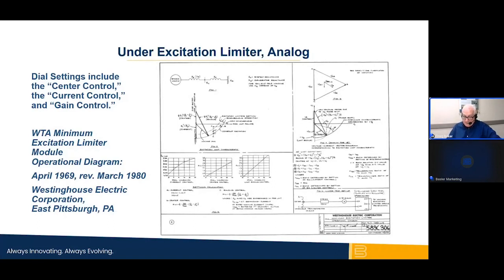The diagram shown here for a Westinghouse UEL for a WTA AVR is associated with instructions for the dial settings. These steps describe constants, such as the utility tie's impedance, X sub E in this diagram, which are assumed values. The UEL's module settings are recommended to have an added safety factor within the confines of the curve.